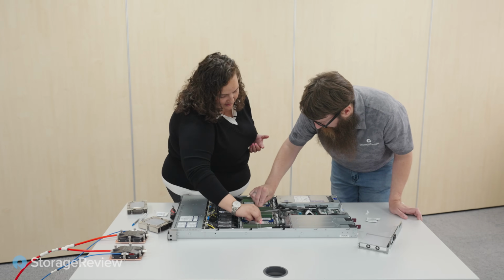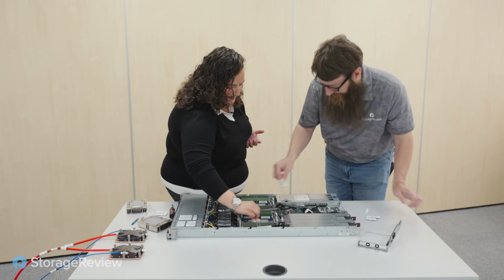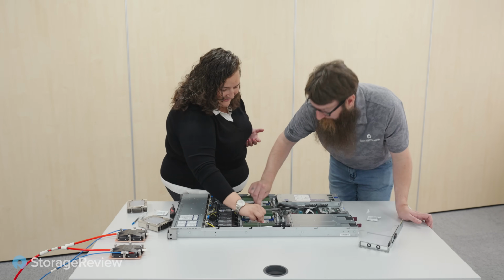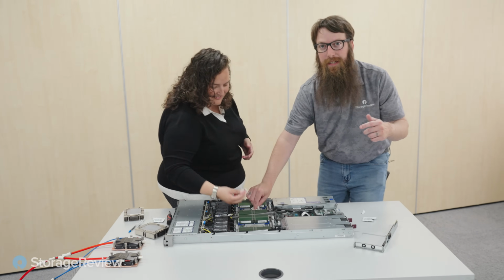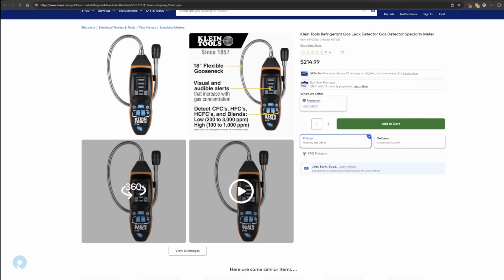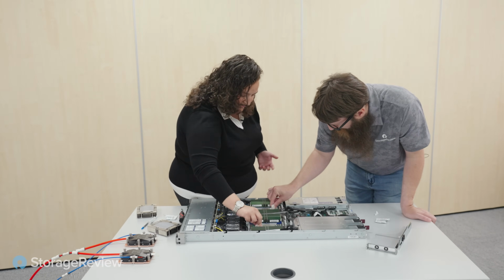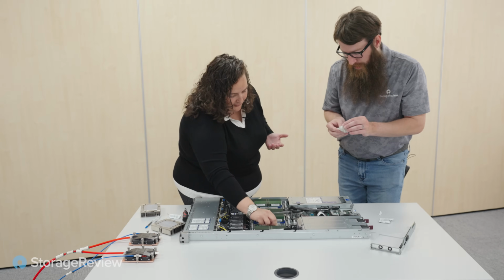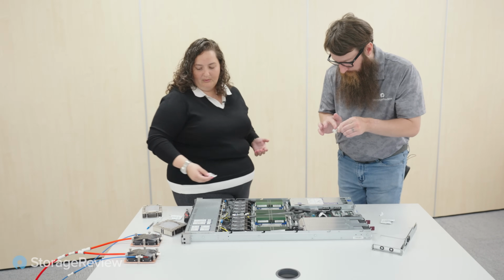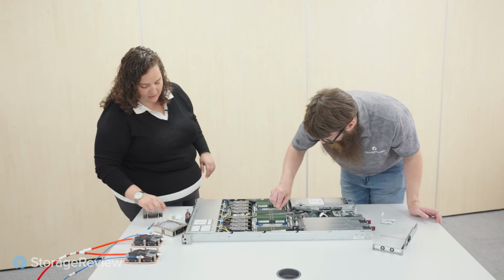Okay. And then, of course, you can find a leak. We usually use a standard sniffer. Do you know what a sniffer is? Yeah. So for those of you playing along at home, Vince is going to put up a little picture of a sniffer. So we're using a sniffer just to try to detect the leak itself. We fix the leak, so it could be just to replace the server kit itself, or it could be sometimes just that someone didn't really plug all the way in, or plug the tubing all the way in.